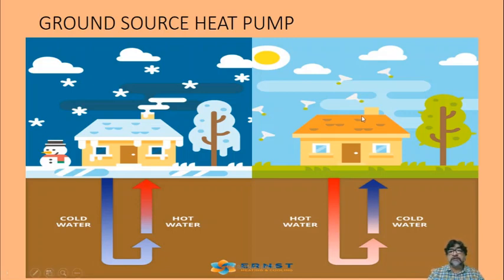The reverse happens in summer. What happens when the outside temperature is higher, let's say 24 to 35 degrees Celsius? Inside the earth the temperature stays relatively constant, 15 to 18 degrees Celsius. So when you pass the warm water in, as it goes there where the inside temperature is 15 degrees Celsius, the pipe's hot water will lose heat and become cold, and it can be supplied as cold water to the household. That means the ground or earth acts as a heat sink, losing heat energy.